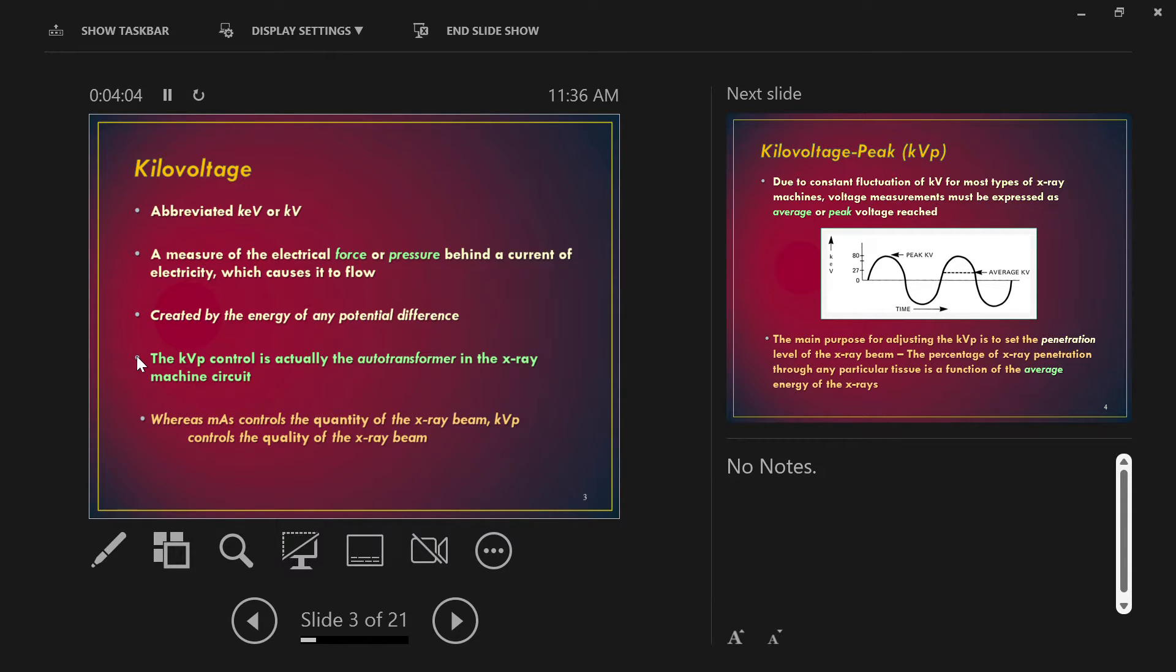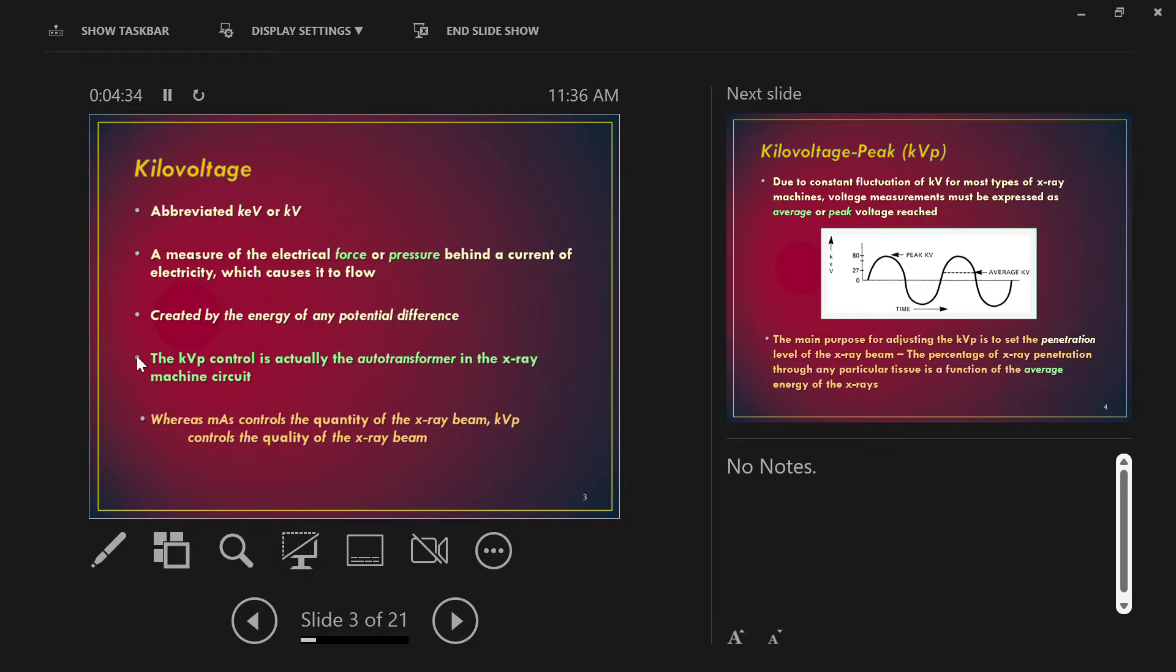KVP control is set in the hardware, the equipment, by something called an auto transformer. Transformers, if you remember, are electrical devices that change voltage. It's Ohm's law - voltage equals amperage times resistance, V equals IR. It's electromagnetic induction and Ohm's law all put together in one concept. We can adjust voltage by adjusting the settings through this auto transformer. Transformers change power, voltage.